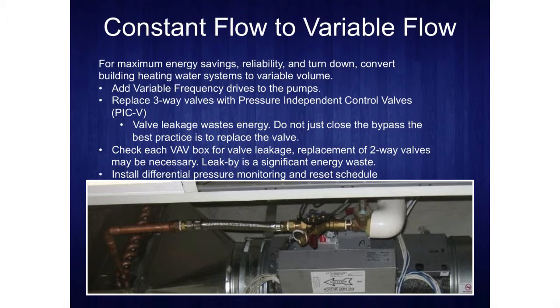Constant flow to variable flow. So if you are in a terminal reheat situation with three-way valves, go from three-way valves to two-way valves and use differential pressure control.